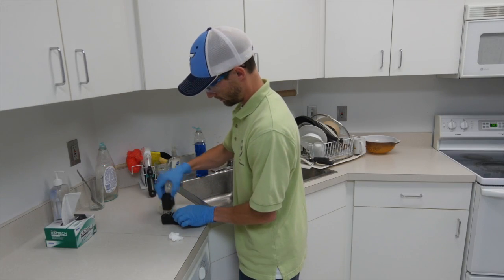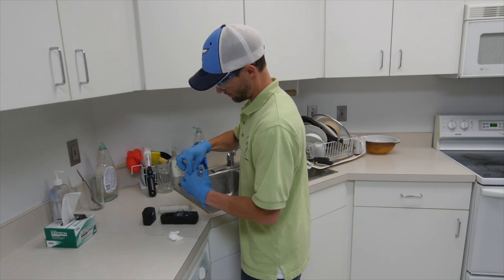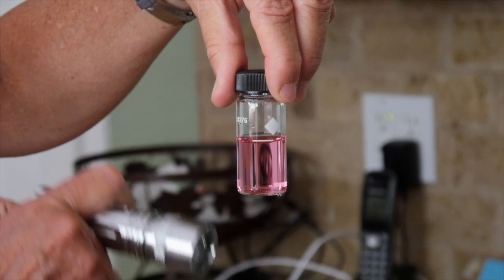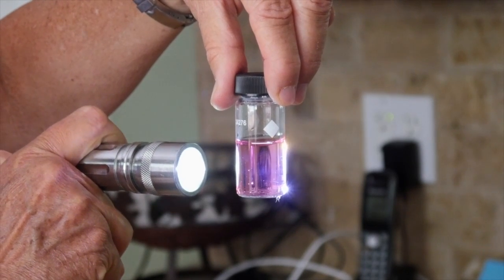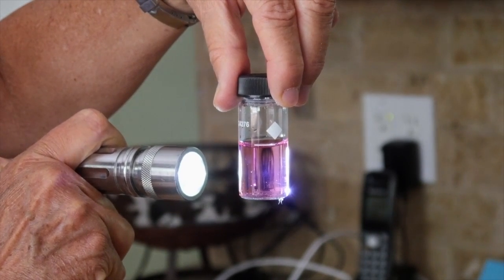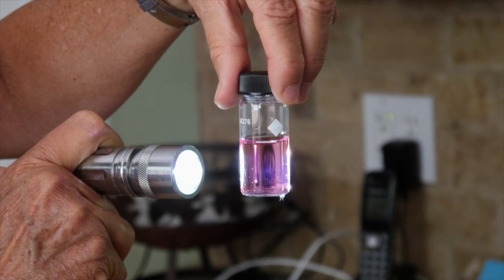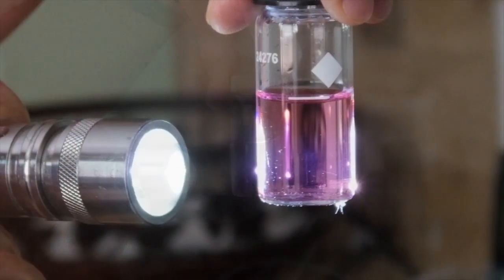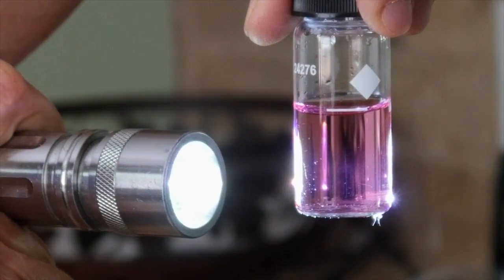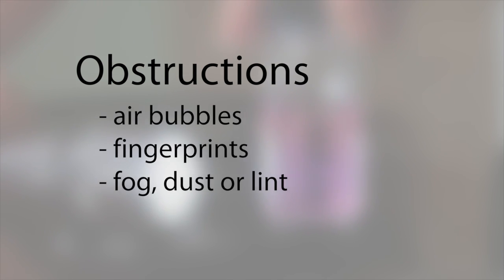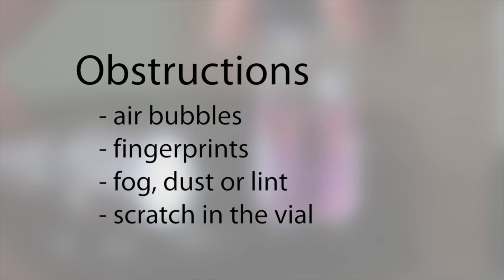The method works by adding a chemical called DPD to the sample. If chlorine is present, a pink color will form. A spectrophotometer works by shining light through a sample and measuring the intensity of the light. The pink color blocks light and the decrease in light intensity is measured. It is important to remember that anything that blocks light can impact the result. This can include air bubbles, fingerprints, fog, dust or lint, or a scratch in the vial.